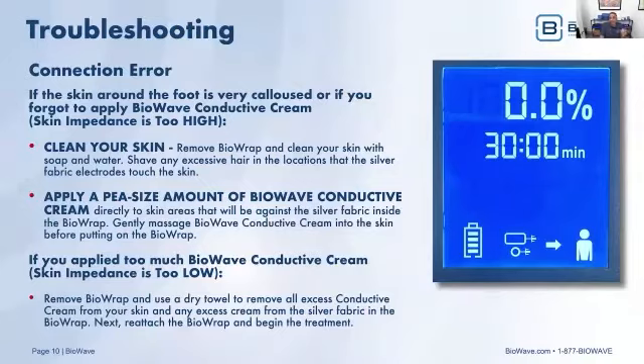On the other hand, if you applied too much conductive cream and there was a lot of white cream still on the surface of the skin, and then you put the BioWraps on, it may be that the skin impedance is too low and the device isn't going to see the electrodes because the impedance is so low. So in that case, remove the BioWrap, take a dry towel, clean the excess cream off of the skin, and clean any excess cream off of the silver fabric on the BioWrap. Then reattach the BioWrap and then restart the treatment.